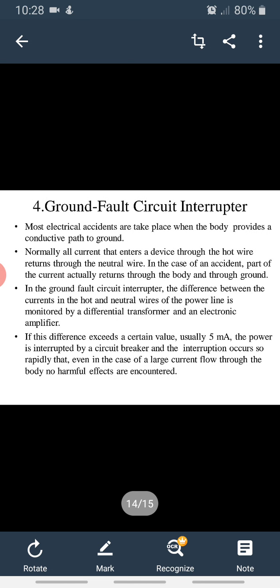And fourth one, the ground fault circuit interrupter. Most electrical accidents take place when the body provides a conductive path to the ground. Normally, all the current that enters the device through the hot wire returns through the neutral wire. In the case of an accident, a part of the current actually returns through the body and through the ground. In the ground fault circuit interrupter, the difference between the current in the hot and the neutral wire of the power line is monitored by a differential transformer and an electronic amplifier. If this difference exceeds a certain value, usually 5 milliampere, the power is interrupted by a circuit breaker, and the interruption occurs so rapidly that even in the case of a large current flowing through the body, no harmful effects are encountered.